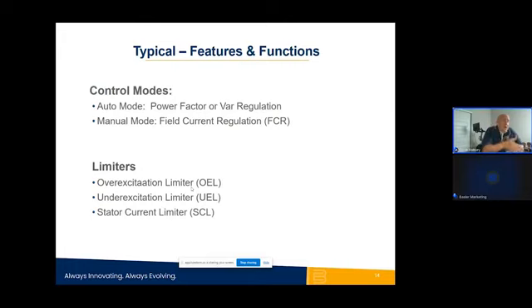Then the DECS products have protection that you can set up for field over voltage or field over current. So there's a lot of tools to use to protect that motor and make sure that it stays in synchronism so you don't lose your process. Same way with the under excitation limiters. That's set up where it's looking at VARs being absorbed into the machine. As you start losing synchronism, the UEL will come into play before your protection will, and try to save that process. Stator current limiter, I don't see that much on synchronous motor applications.